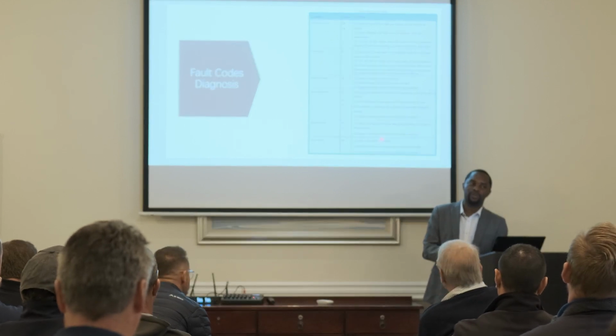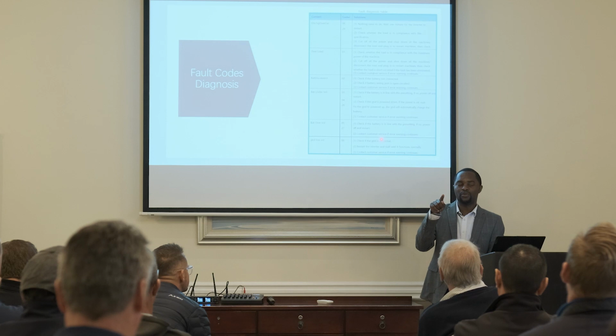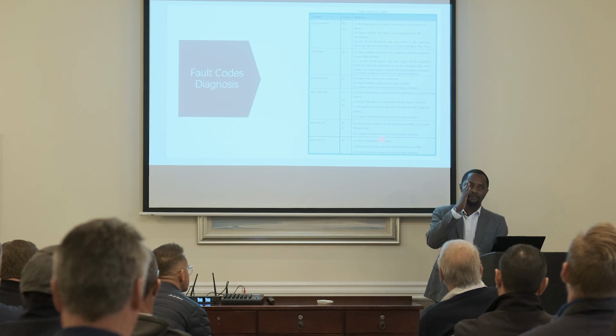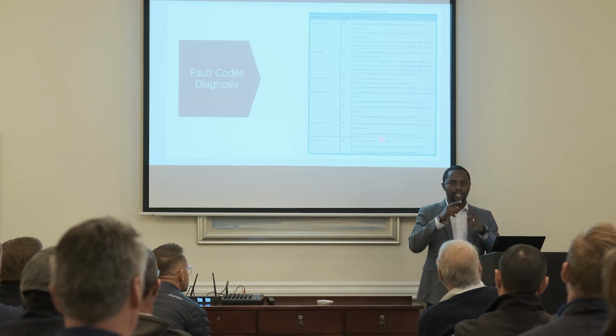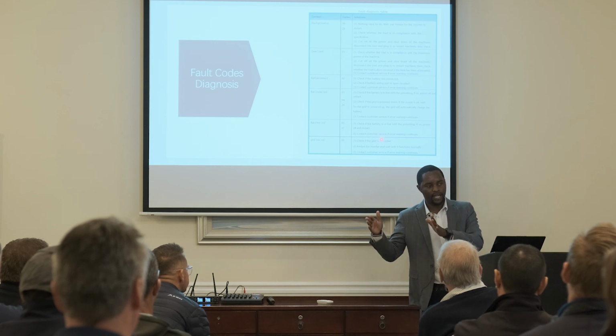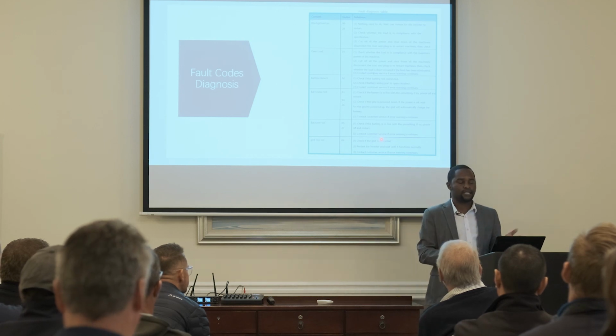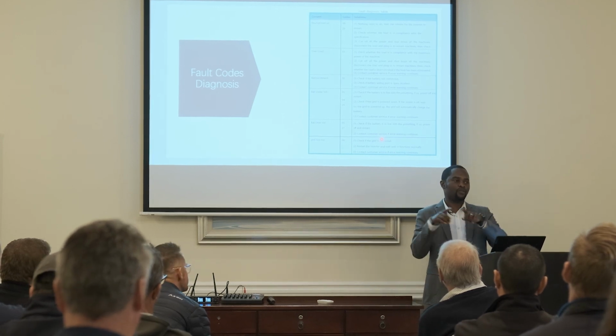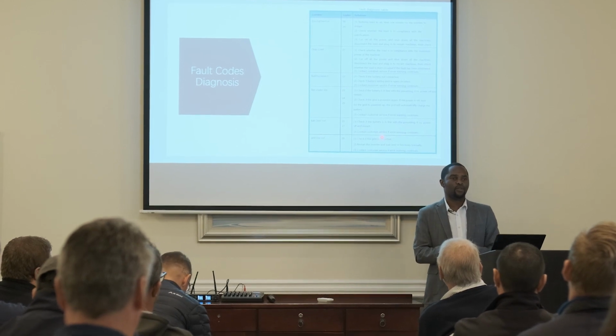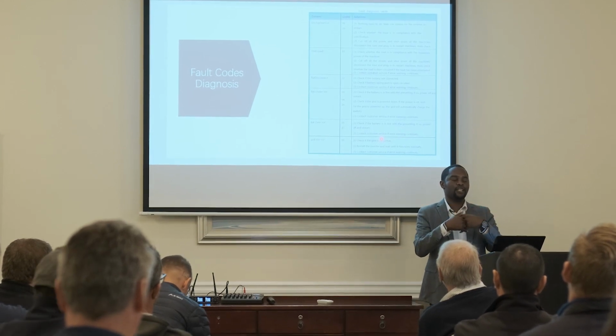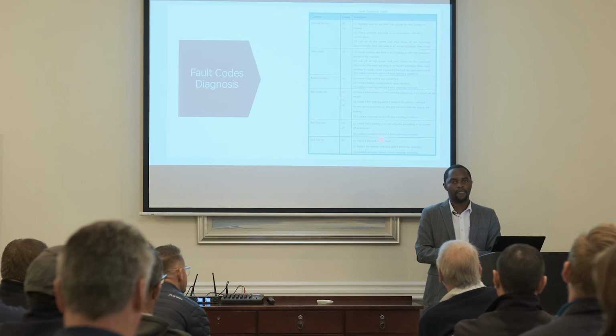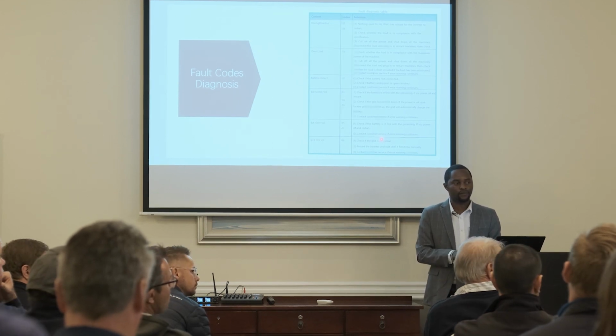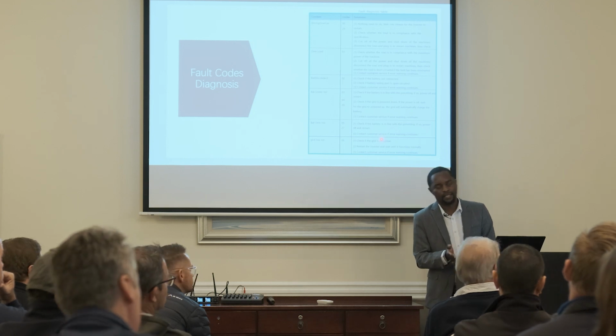I think it's an important point. When you're paralleling, you're combining those outputs. So make sure that the live on port 1 is looped with the live on port 1 on the last slave. You can't take all the lives and put them together. You short those inputs internally and your inverter will give you an alarm. The neutral earth bonding relay is the same thing. Yeah, the same thing, standard.